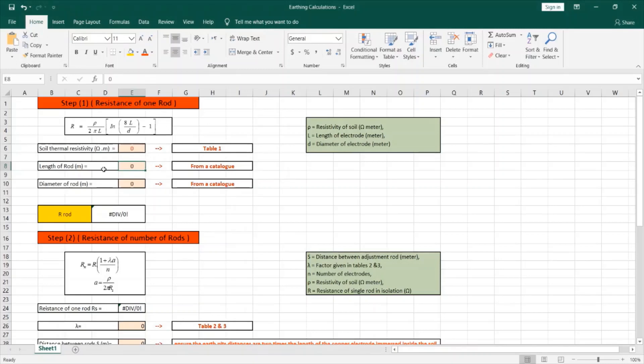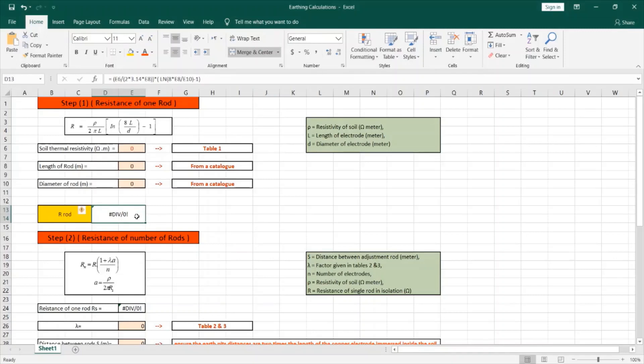This Excel sheet divides the calculation process into three steps. The first step is to obtain the resistance of each rod using this formula: resistivity of the soil divided by 2π, multiplied by the length of the rod, multiplied by the natural log of 8 times the length of the rod divided by its diameter, minus 1. We will enter our values into these cells with the help of an external table and catalog, and the result will be calculated at this cell.